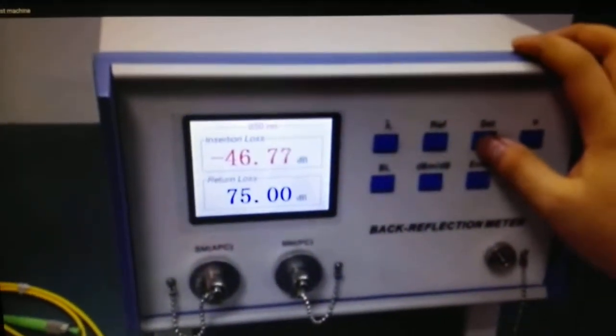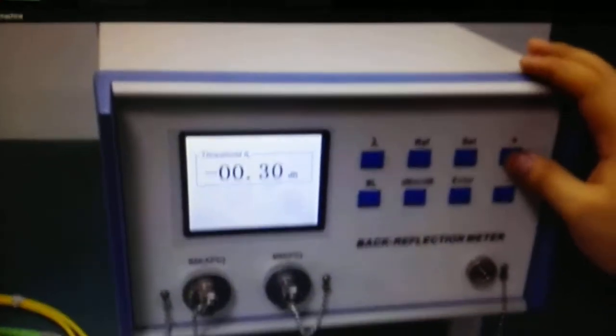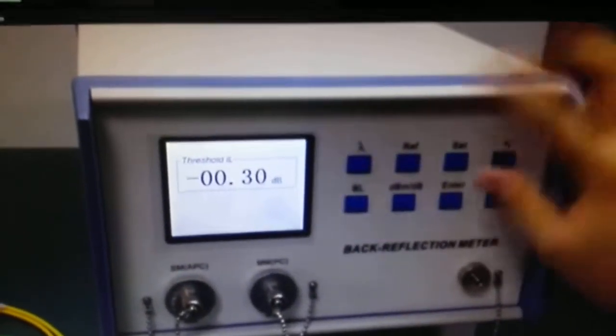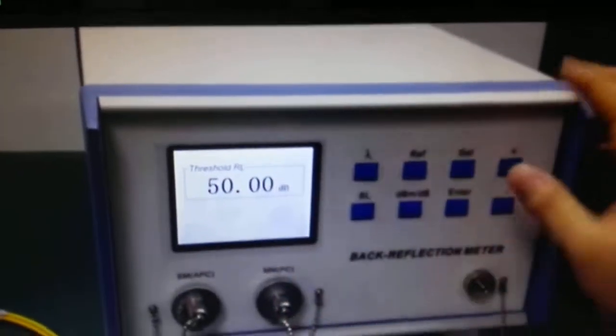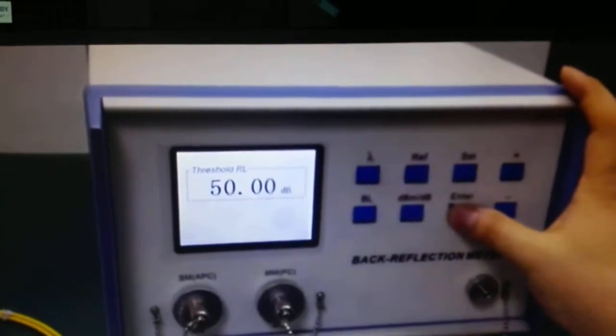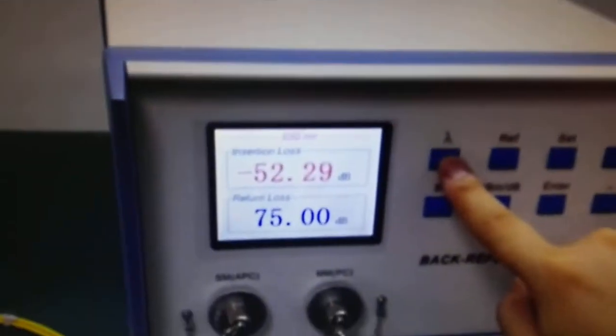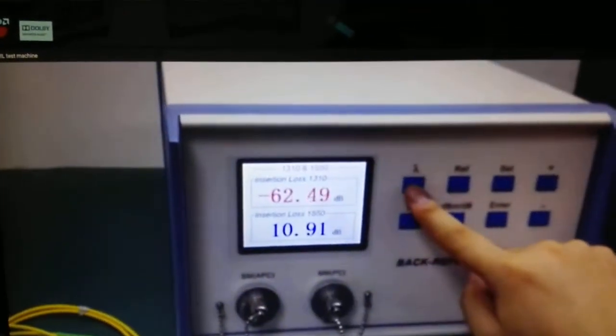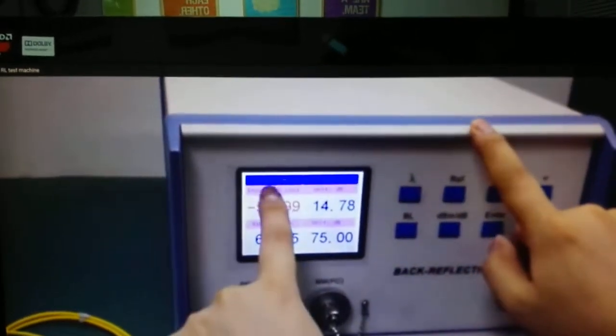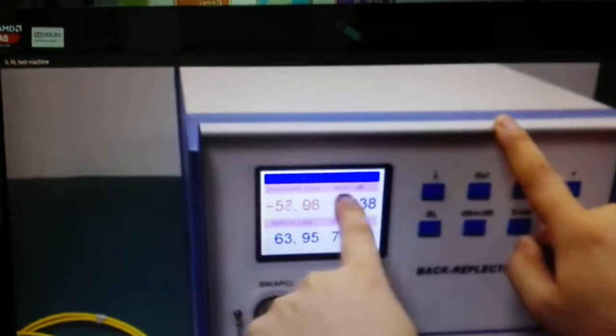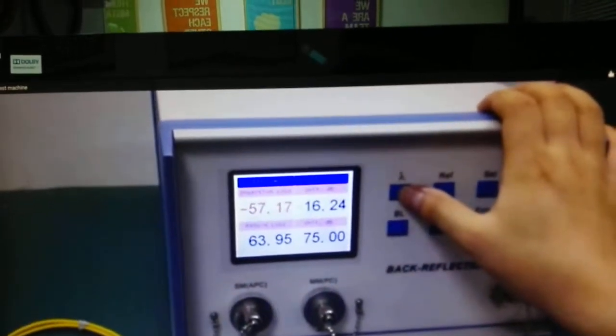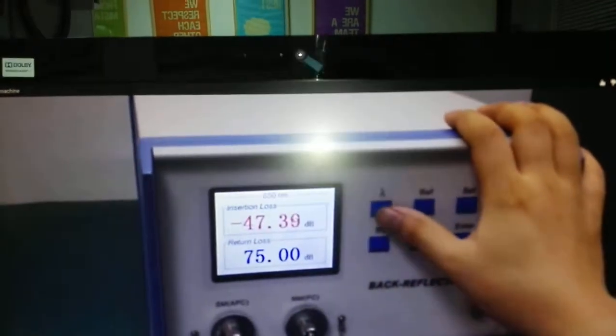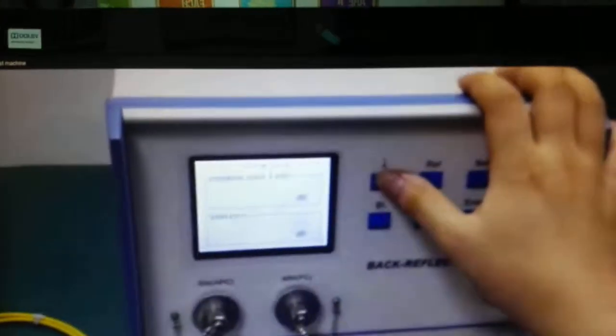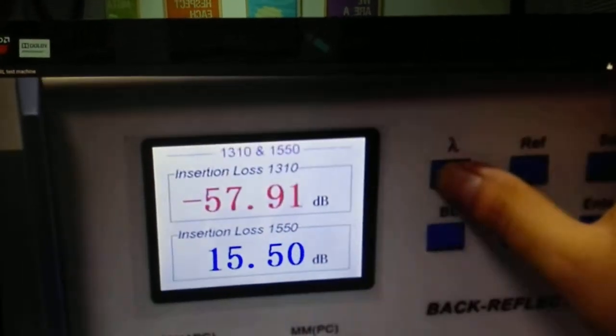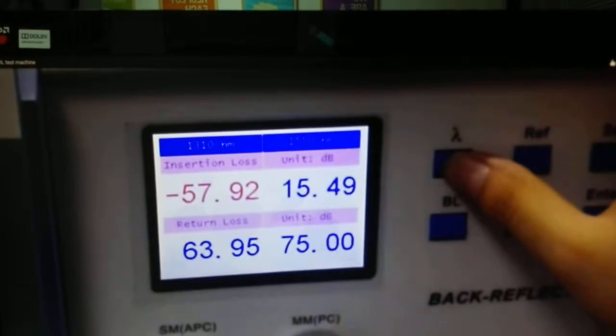First, set the insertion loss. The insertion loss should be below 0.3 dB, so set it to 0.3, and set the return loss to 50 dB. Then set the wavelength. Lambda means wavelength. You can see the two wavelengths, single mode and multi-mode, and this is a different display for the single mode and multi-mode wavelengths. This just shows you the different display for the wavelengths.